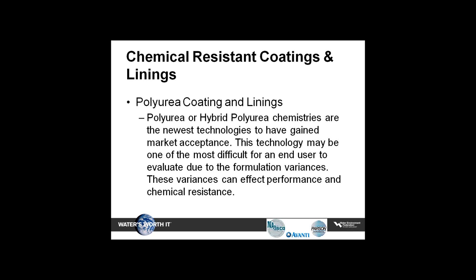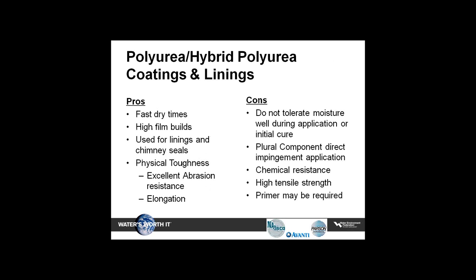Polyurea coatings and linings have been the newest technology but have been around for a while. There are so many different formulations that can affect chemical resistance. The pros are they're very fast dry, have very high film build, are used for linings and chimney seals, are physically tough with very good abrasion resistance, and very good elongation up to 530%. The cons are they don't tolerate moisture at all and must be applied with plural component equipment which is sometimes bulky. Although there has been some robotic plural component in the market, some have very poor chemical resistance, depending on formulation. A primer is generally always required.